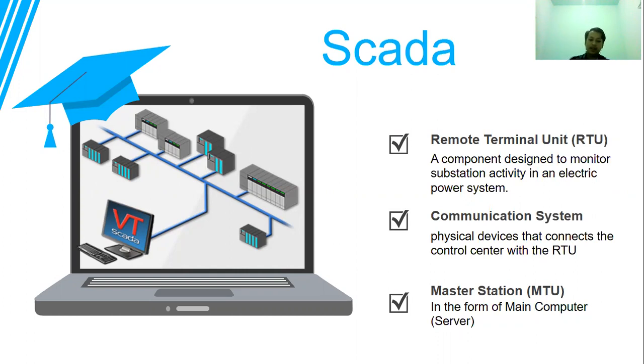RTU or remote terminal unit is a substation of SCADA that functions as the terminal of the result of measurement. It can be measuring a device, can be control and monitoring, and so on. The communication system is a way to communicate data from the RTU to the MTU. On the RTU, which is located far from the control center or MTU, the communication system is usually by radio. The master station or MTU is a computer system in charge of routing data from the RTU. This MTU is also in charge of receiving data from each RTU to be transferred to the HMI.